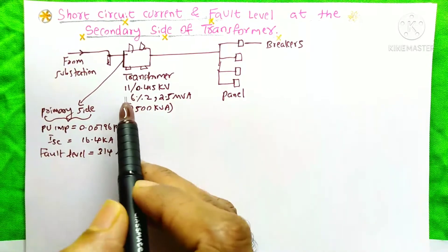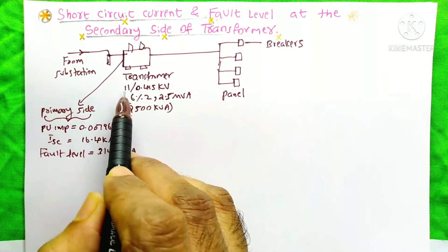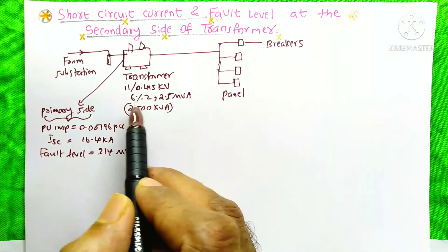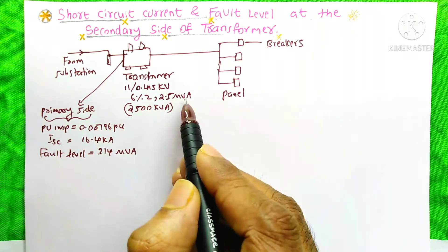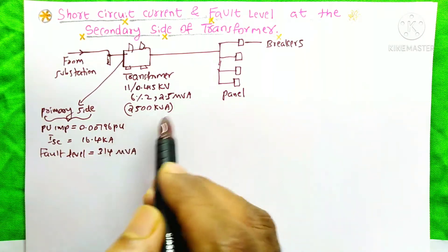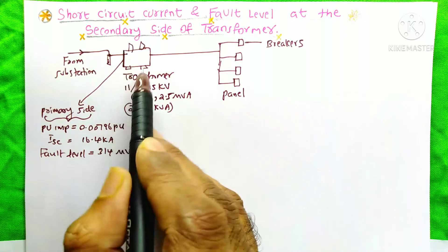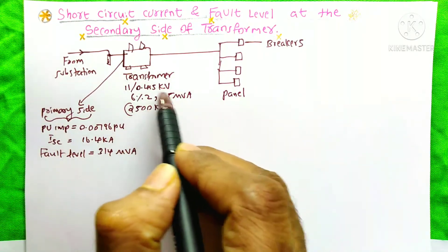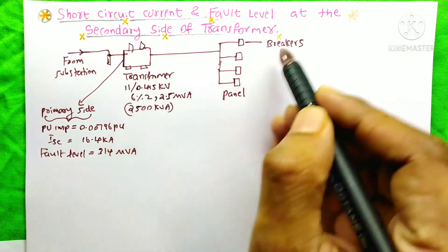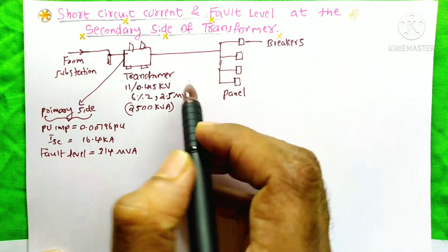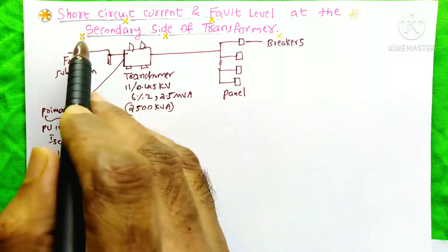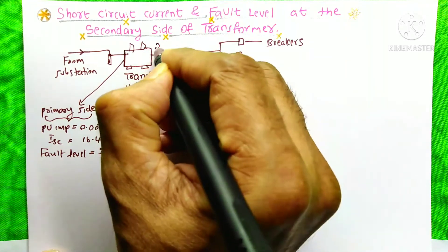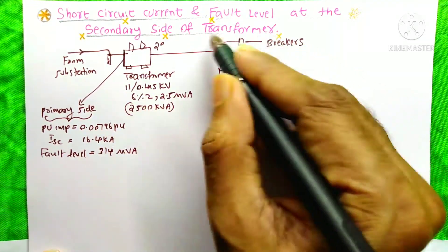Suppose this is our transformer. It converts 11 kV to 415 volt, that is 0.415 kV, with 6% impedance and 2.5 MVA power. 2.5 MVA means 2500 kVA. This transformer is getting power from the government substation, and after it converts to 415 volts, it directly goes to the control panel. In this tutorial, I am going to calculate the short circuit current and fault level at the secondary of this transformer and also at this panel.